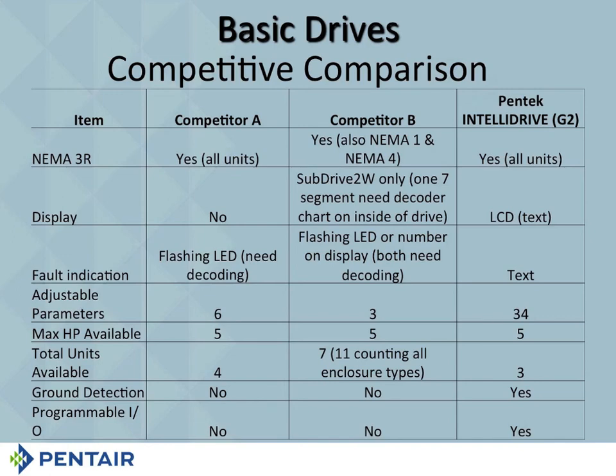Maximum horsepower is 5 for everybody. Total number of units, here you want a small number. 4, 7, count all the enclosure types, and they have 11. We have 3. So you only have to keep 3 different ones in stock, and then you've got one of each. Ground detection, they don't have it. We do.